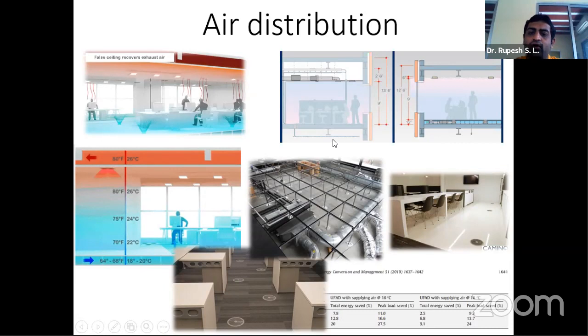So if we look at the overhead system, typically it's a mixing system. So it achieves a homogeneous mixture of air at about 24 degrees across the room itself. But an underfloor system would be a stratified system. That means my air, which may be entering at 20 degrees, or my grill temperature could be as high as 20 degrees, as against 16 degrees or 17 degrees in an overhead system, which would be the grill temperature. I already achieved a 4 degrees delta T on my grill temperature.